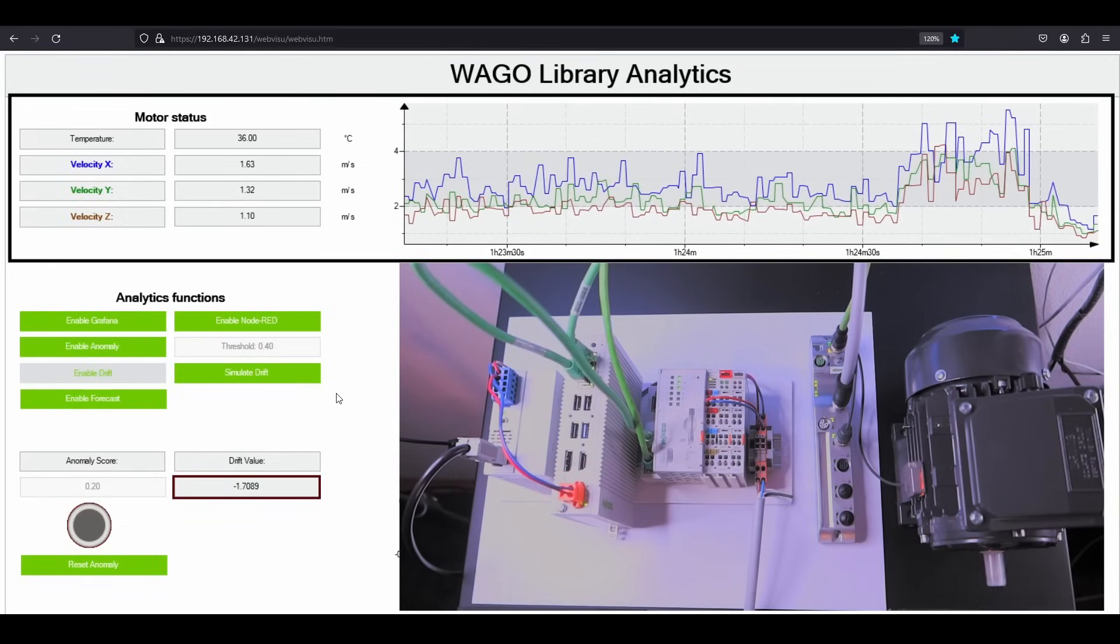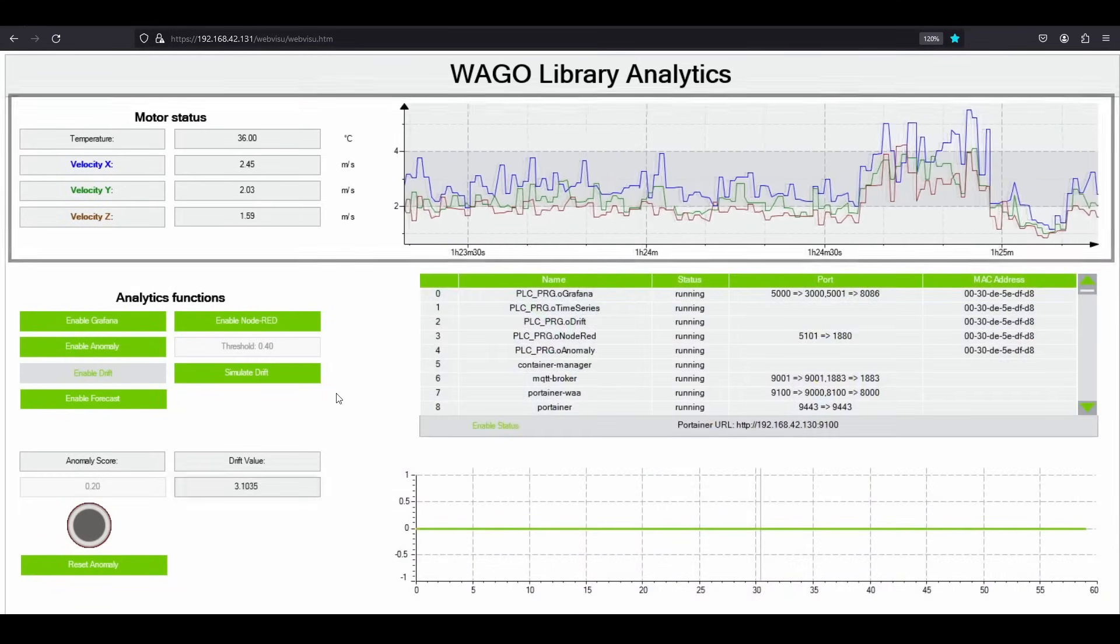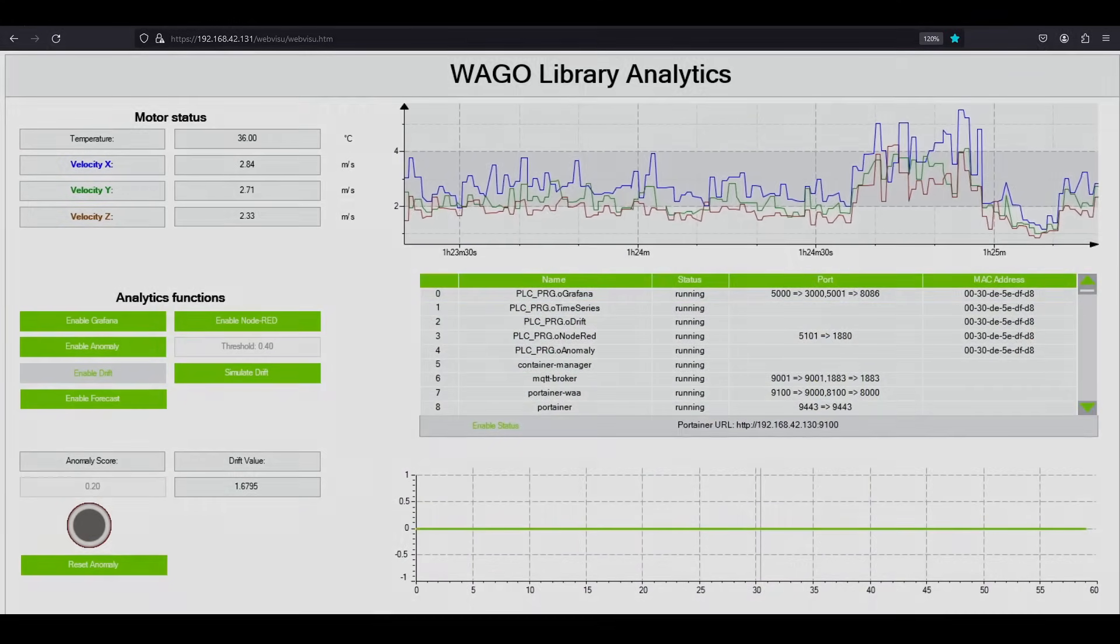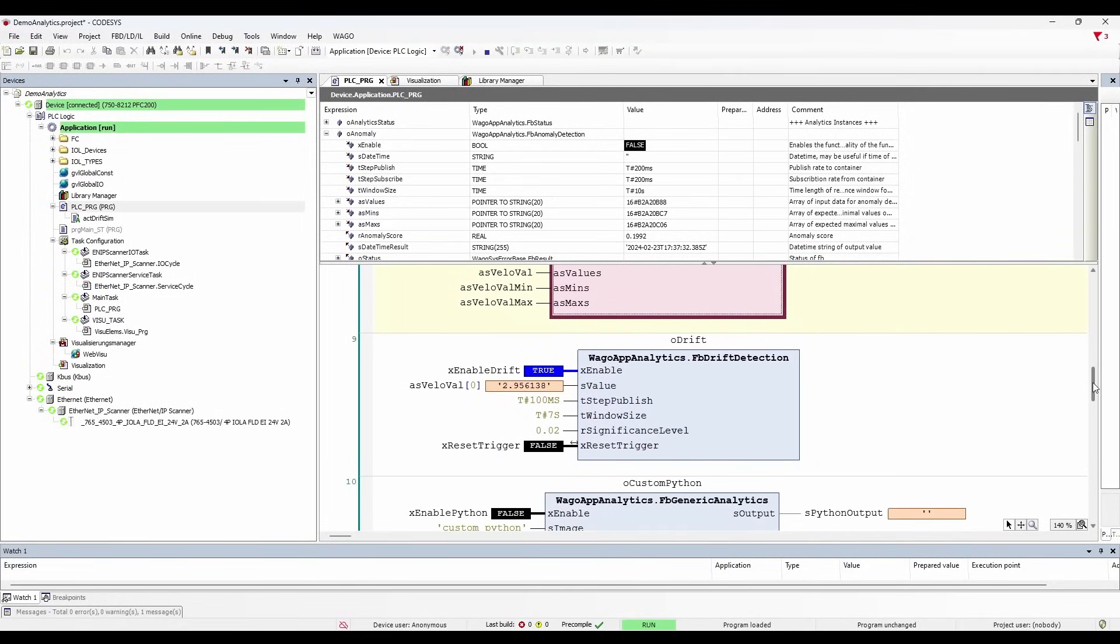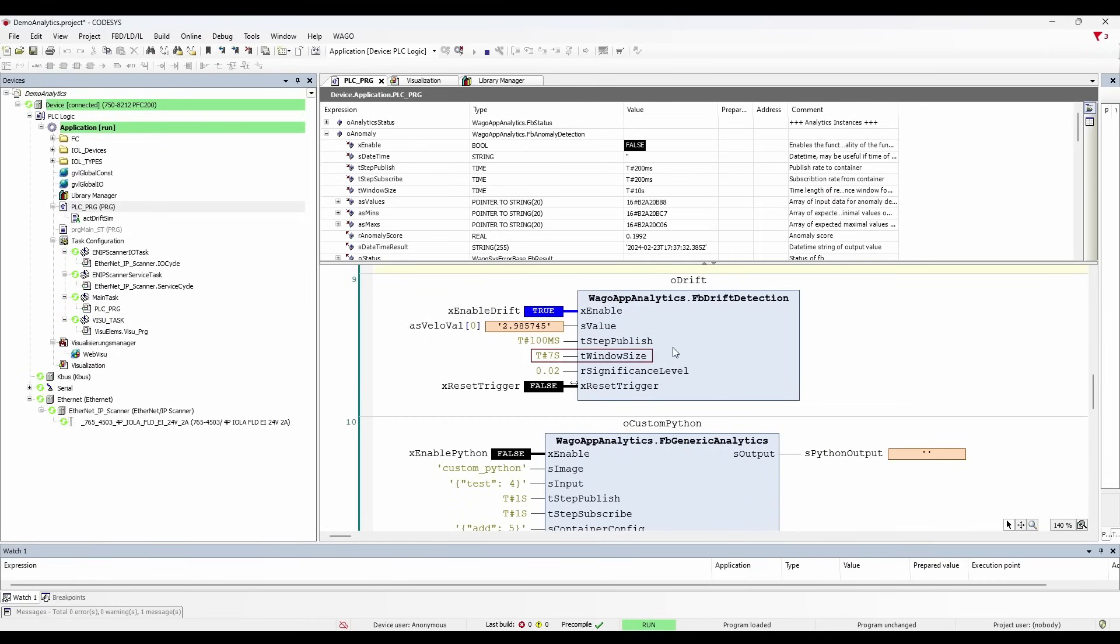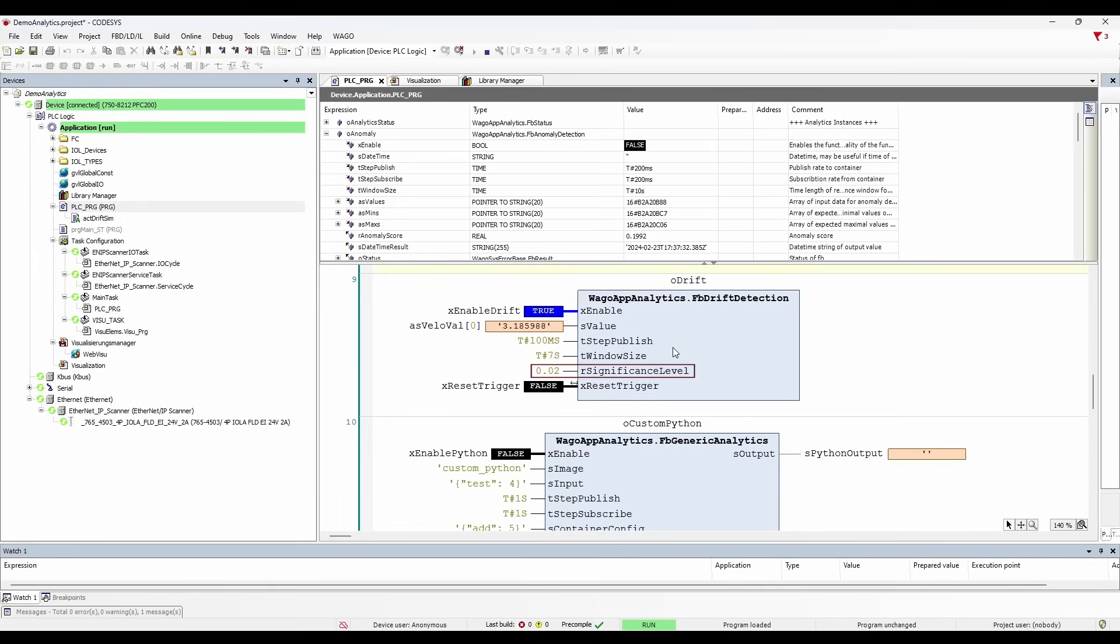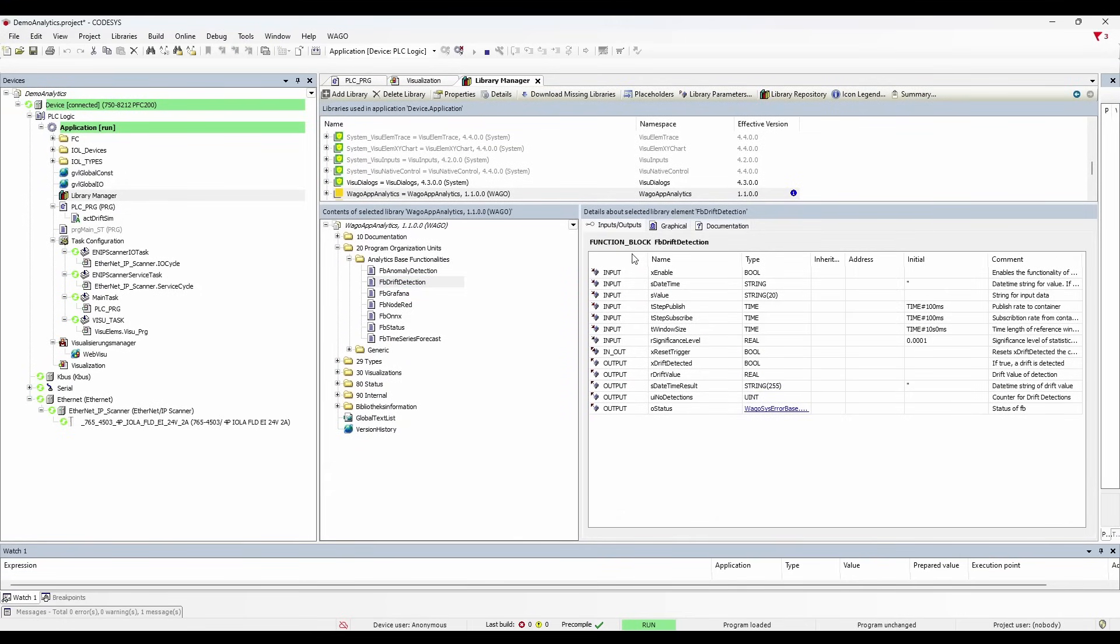So you can imagine how the slow and gradual change reflect the drift value. You have to do absolutely nothing. The Docker containers does all the magic to give you the drift value. So let's see how we are getting the drift value in the PLC program. In this block, I am sending VRMS as string data type only for the x-axis. The publish and subscribe time is set to 100 milliseconds and a window size to 7 seconds. The window size is the time for which the motor is being observed for drift calculation. This is just the test value. Generally, the window size is in hours, days, weeks, or even months for long-term analysis. Or this interval can also be aligned with your maintenance schedules. The significance level, which is set to 0.02, is a statistical measure that indicates how confident we are that a given drift is not due to random variation. Similarly, you can learn more about these function block parameters with the provided documentation.